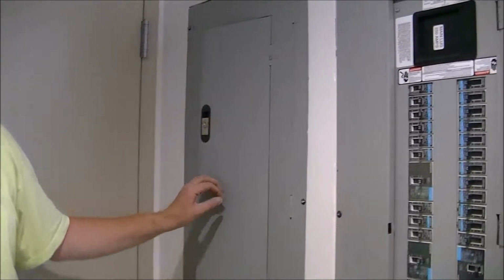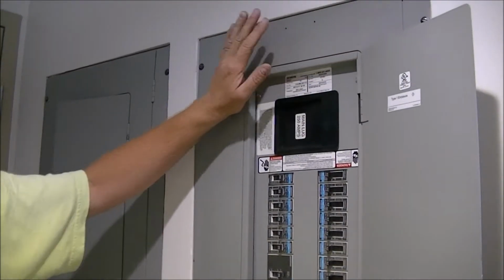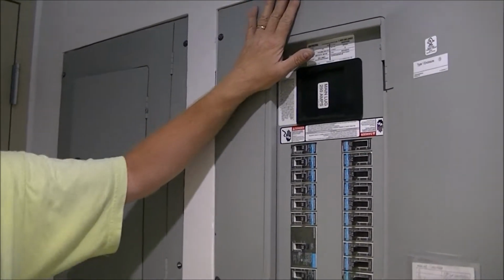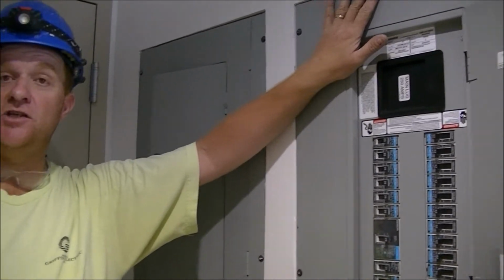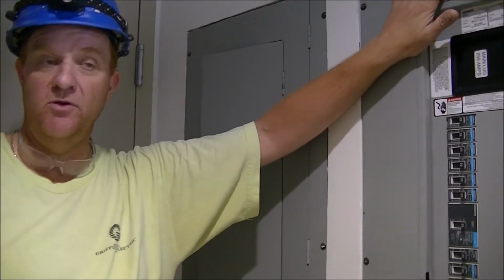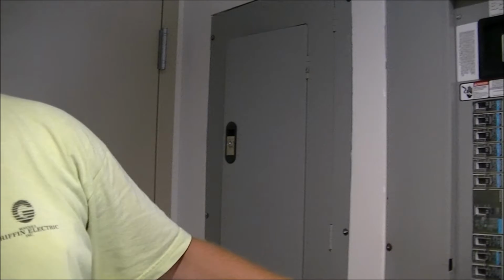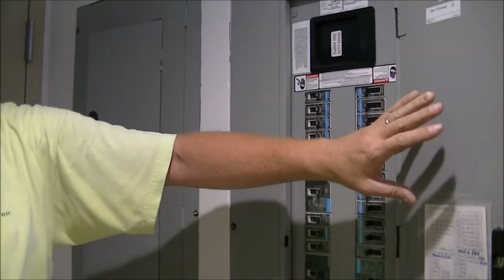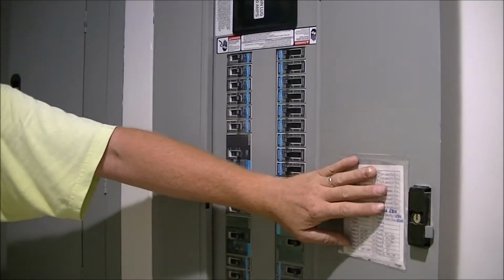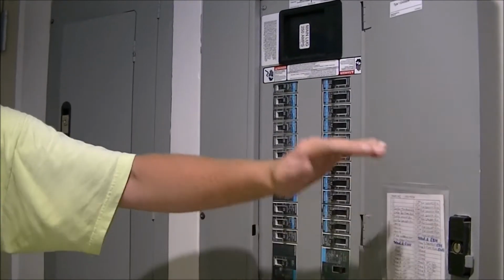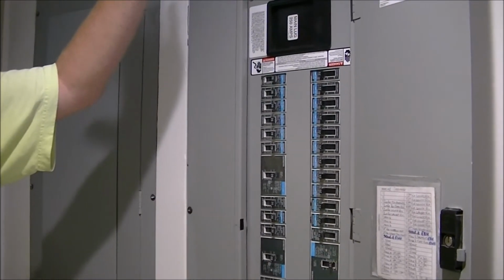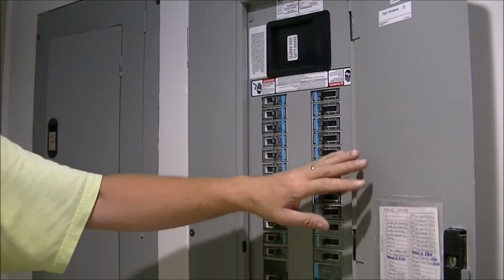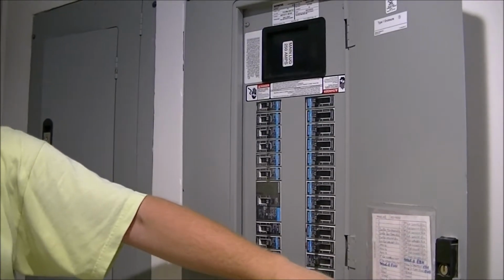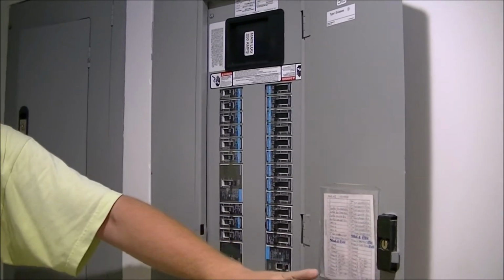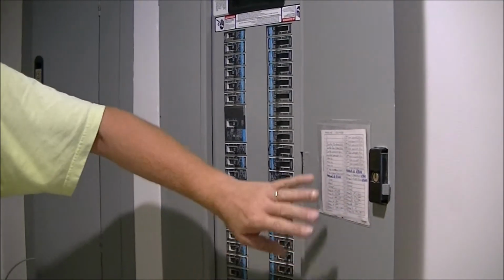This is the high voltage panel, 480-277, this is H2, fed from the old custodian's area downstairs, the panel we just looked at. This does the lounges and laundry fan coil units all the way up from the third floor to floor 19. It also does the heating on stair A and stair B, all coming out of here as well.